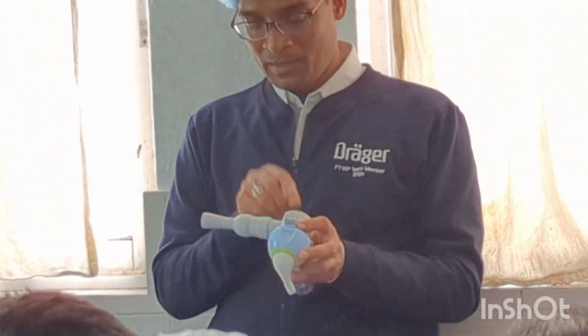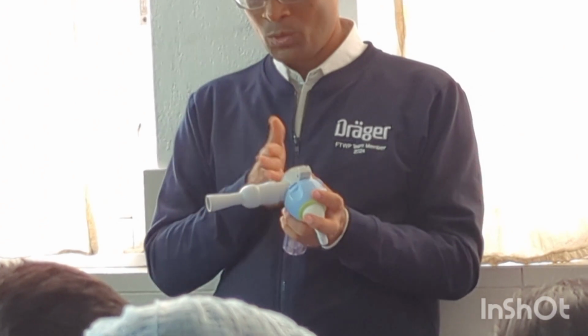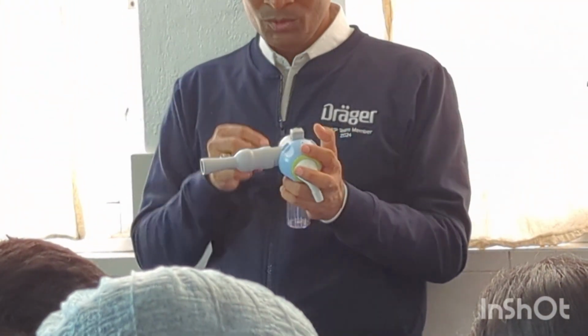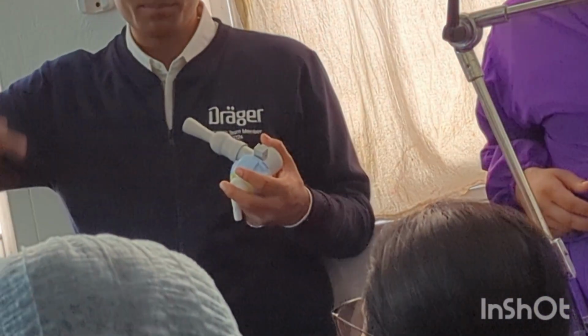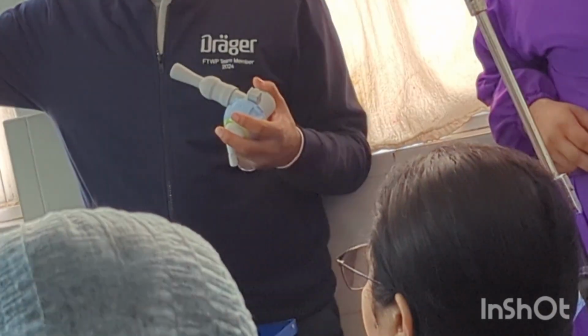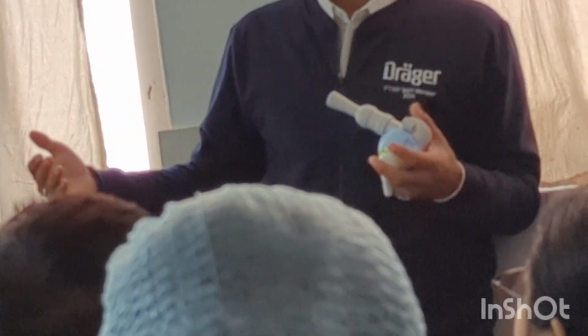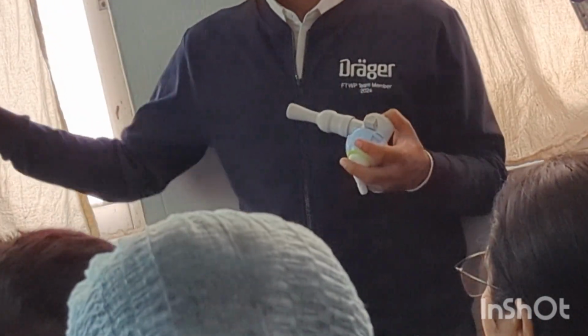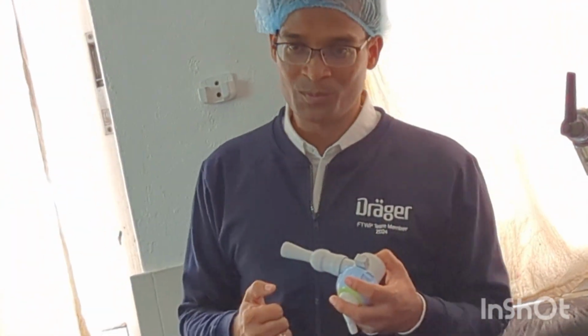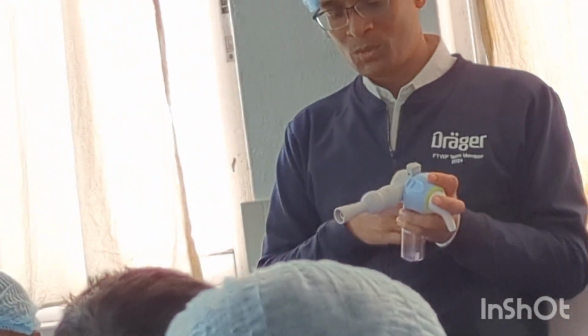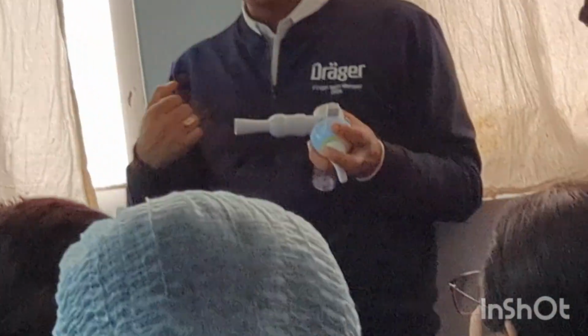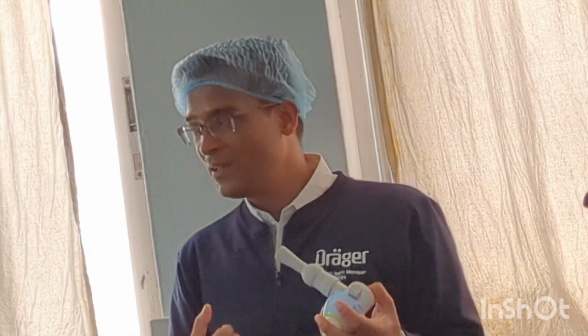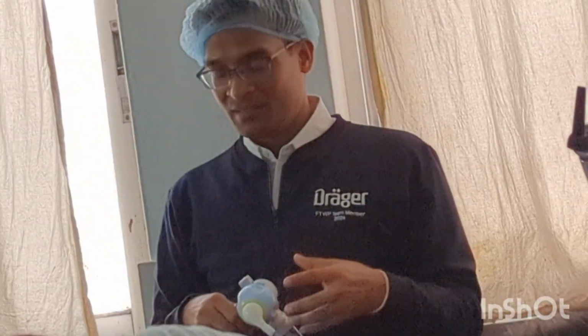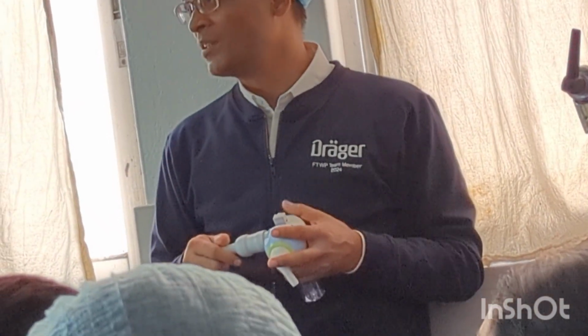And what is the purpose of passing this flow? When this flow passes through this venturi, it will actively pull. Like a venturi, when there is a high flow through some vessels, it creates a negative pressure at the side. Like when a train moves very fast, if you stand just near the train, there is a chance it will pull you. They use the same principle here. When the gas flows through this, it will also pull the expired gases, so you are actively pulling the expired gases during HFOV.